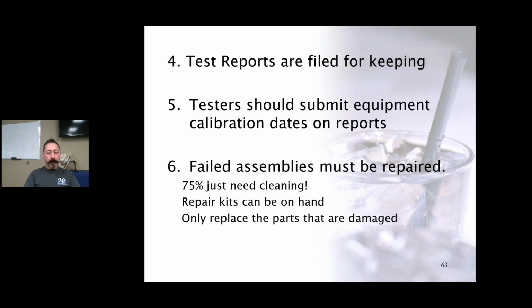So again, only replace the parts that are damaged. Now, some people say, well, we replace the whole set of parts. That might be fine on a 3/4 inch or 1 inch backflow preventer, but when these backflow preventers get large, up to 10 inch or 8 inch or 6 inch, these are extremely expensive parts. So if the other parts are functioning, and we can show that in a test report, then really we're only repairing the damaged or malfunctioning components.